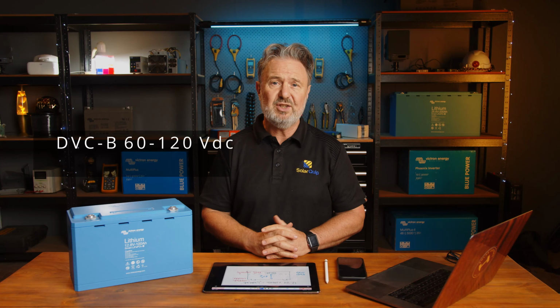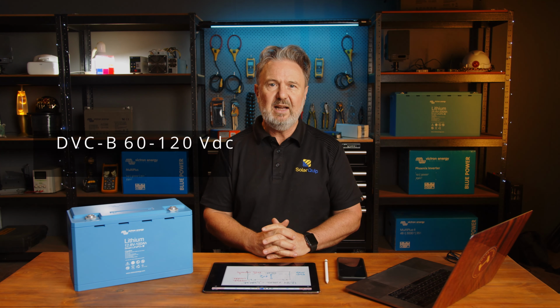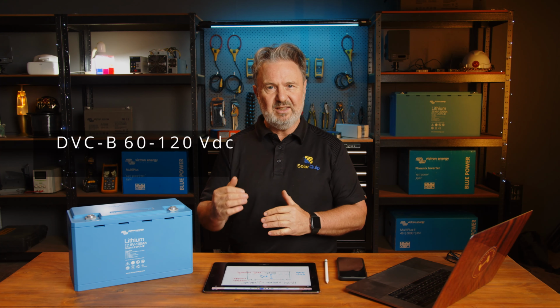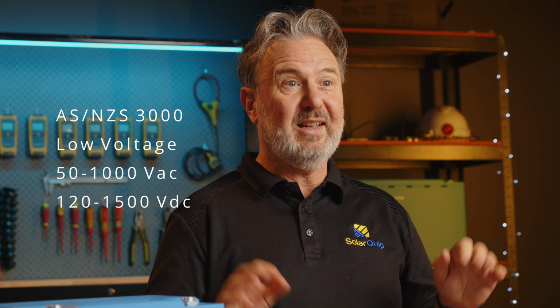Once you go over 60 volts, up to 120 volts DC, you're in decisive voltage classification B, or DVC-B. The next category, DVC-C, covers over 120 volts up to 1500 volts DC. Both DVC-B and DVC-C are deemed equivalent to low voltage. Low voltage sounds safe, but in our standard AS/NZS 3000 it actually means licensed electrical work—it's dangerous, likely a shock hazard or even a potential electrocution hazard. So we deem that a high level of risk, and safety is paramount.